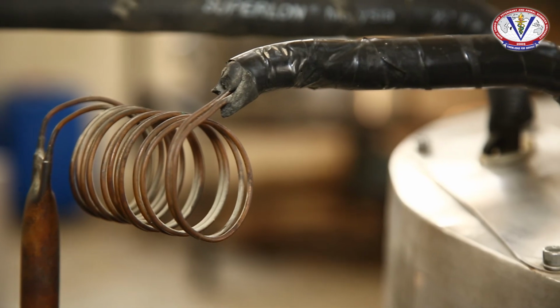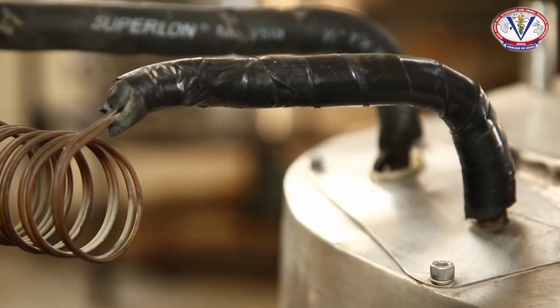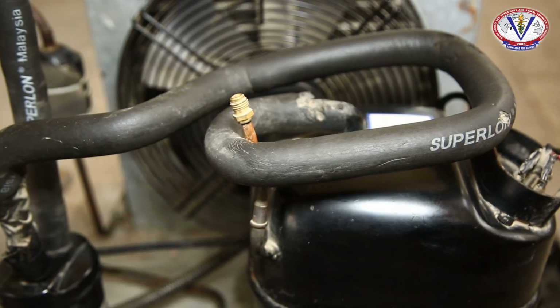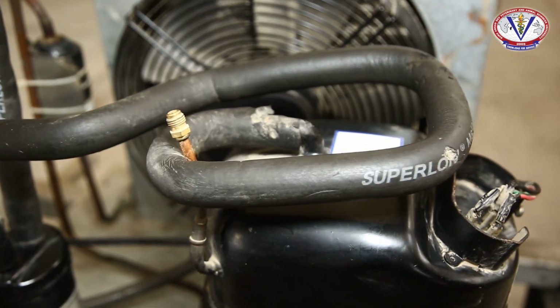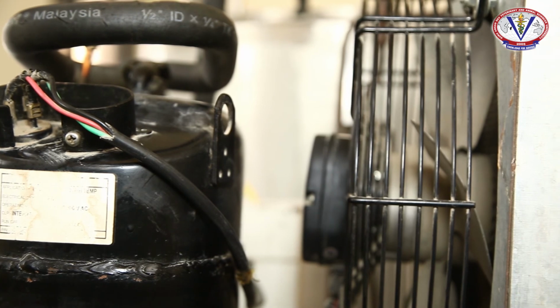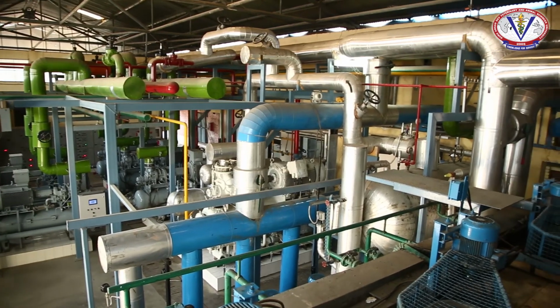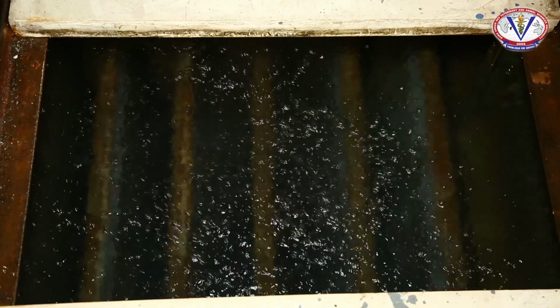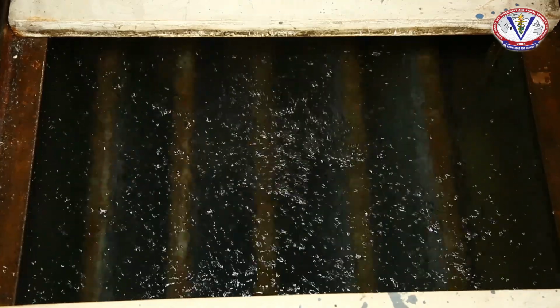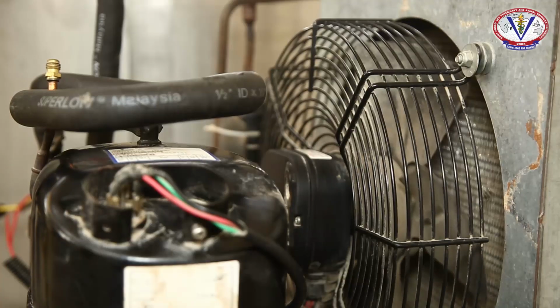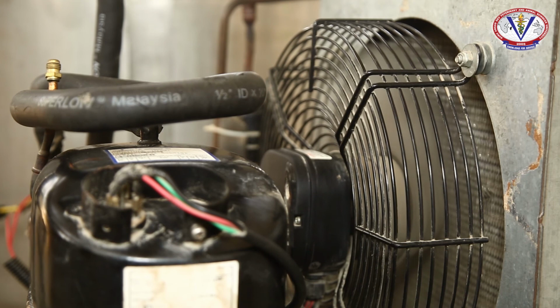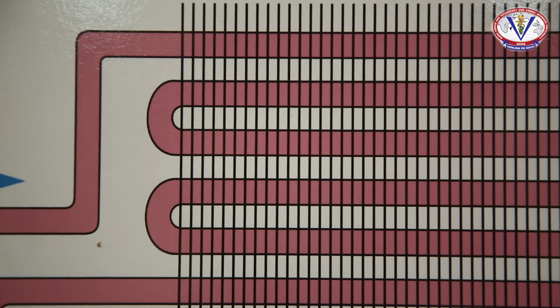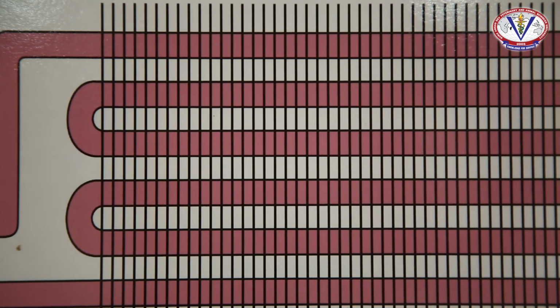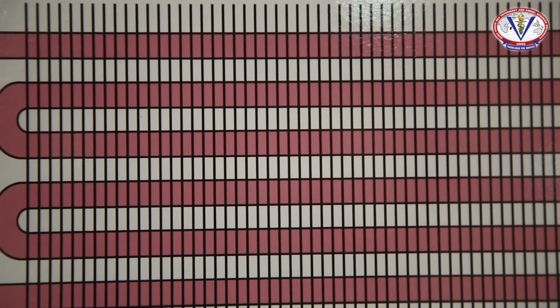The purpose of the expansion valve is to transfer refrigerant from the high pressure to the low pressure side, without losing the enthalpy of the refrigerant. Another more important thing is that effort should be made so that all of the refrigerant is in liquid form while entering the evaporator, and in vapor form when leaving the evaporator. By doing this, maximum refrigeration effect can be achieved with the same compression system and the same condenser system.